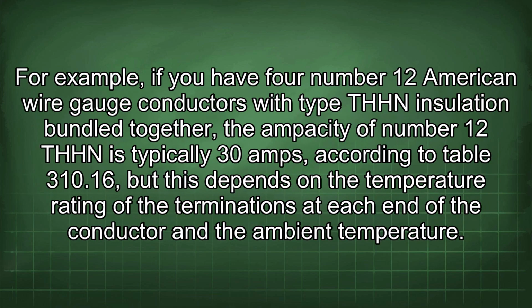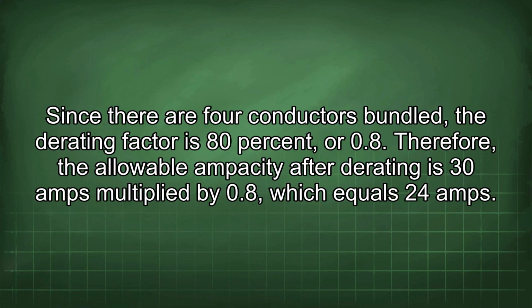For example, if you have 4 number 12 American wire gauge conductors with type THHN insulation bundled together, the ampacity of number 12 THHN is typically 30 amps, according to Table 310.16, but this depends on the temperature rating of the terminations at each end of the conductor and the ambient temperature. Since there are 4 conductors bundled, the derating factor is 80%, or 0.8. Therefore, the allowable ampacity after derating is 30 amps multiplied by 0.8, which equals 24 amps.